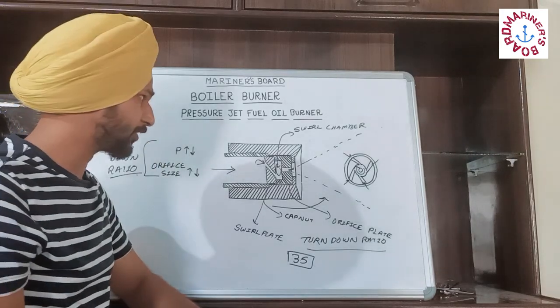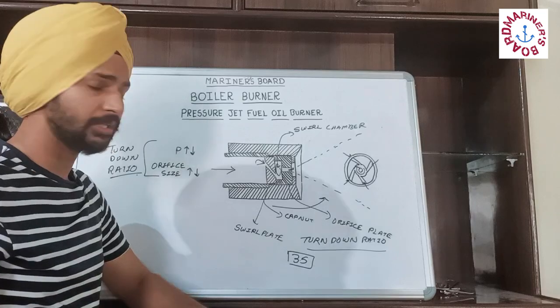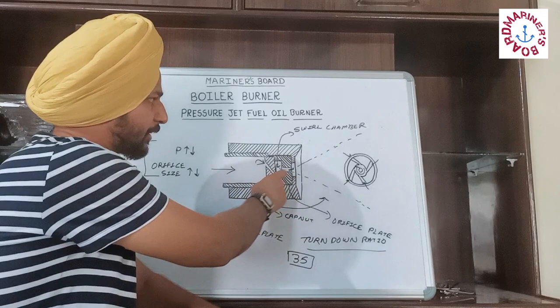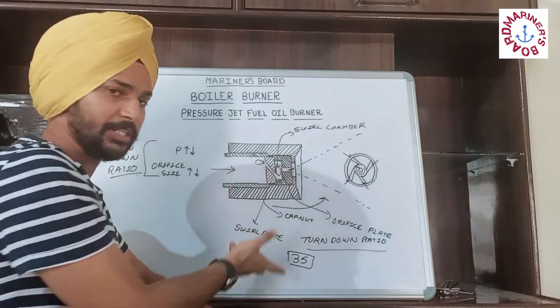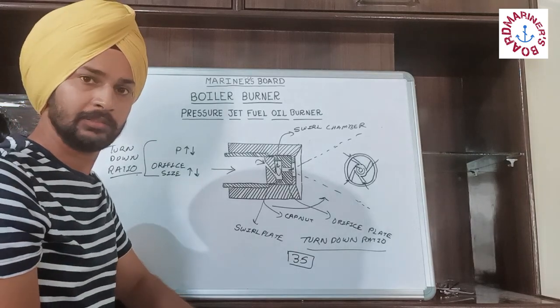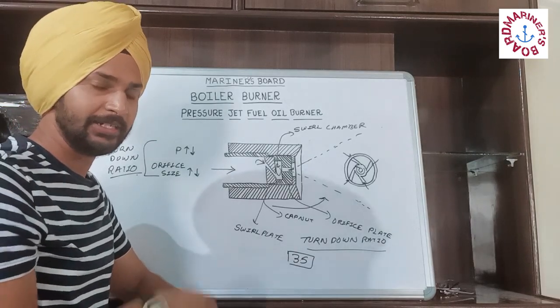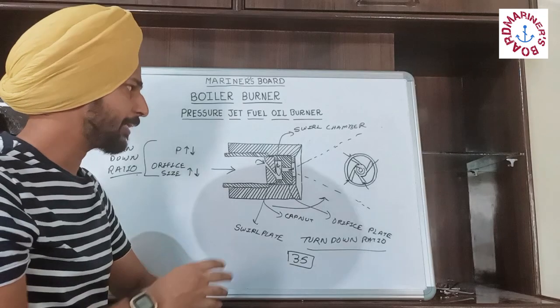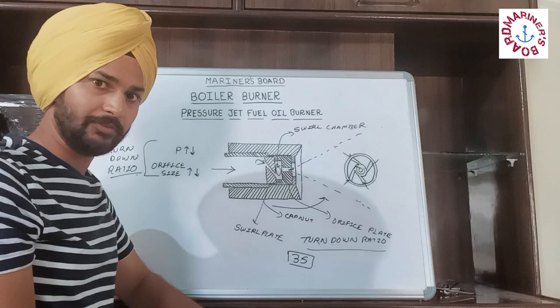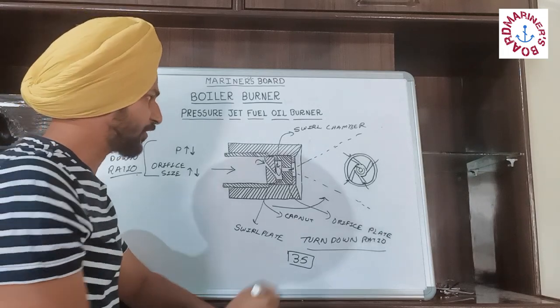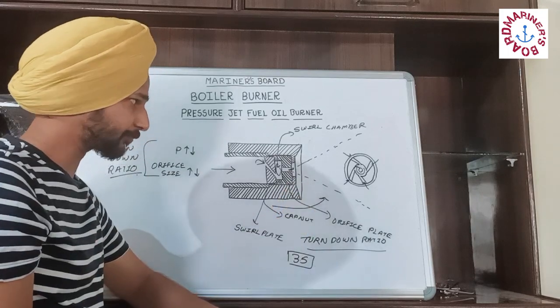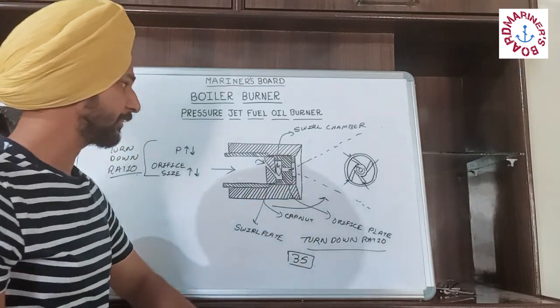For controlling the turn down ratio of this burner, we can either increase or decrease the pressure, or we can change the size of the orifice in the orifice plate by opening it and putting a new orifice plate. This design is not very efficient because every time we have to control the turn down ratio, we have to open the cap nut, open the orifice plate, and put a new orifice plate — so this design has its own disadvantages. The same is the case for the pilot burner studied in the basics: it also has the swirl plate, swirl chamber, and orifice plate.